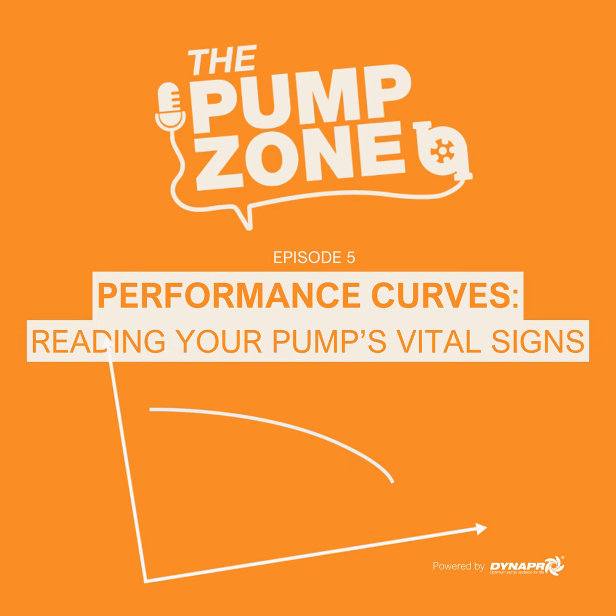If the pump is moving a massive amount of water but gets starved of input pressure, the water inside literally boils at room temperature. Wait, really? It boils just from a pressure drop? Yeah, vapor bubbles form in the fluid. And when those bubbles hit higher pressure zones inside the pump, they violently collapse against the metal impeller. And that's cavitation. Exactly. That implosion will literally eat away solid chunks of metal. So by just throwing the valve wide open, you could basically burn out your electrical motor and tear the pump apart with boiling water bubbles at the same time.